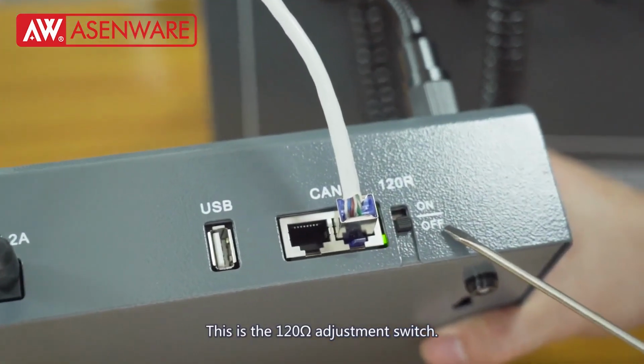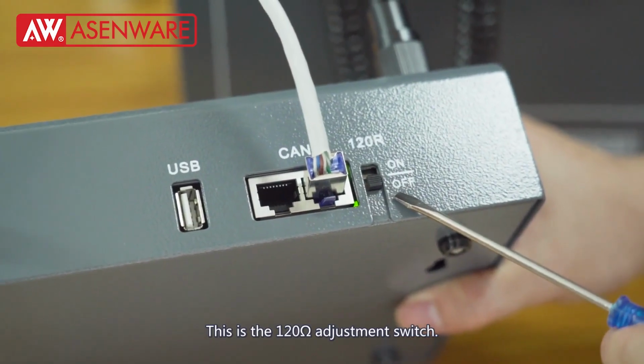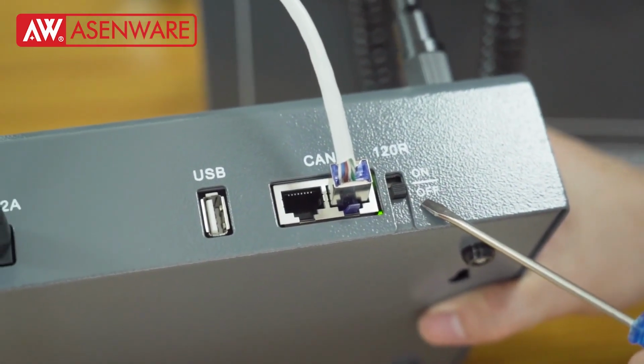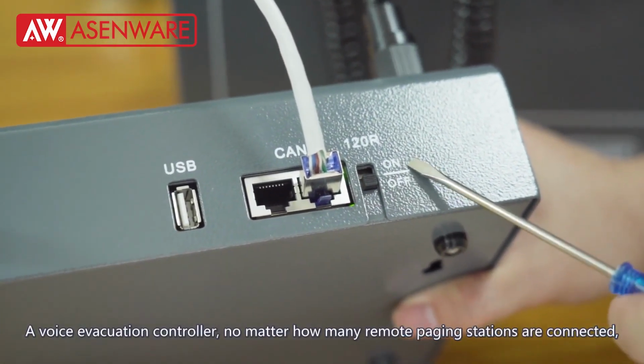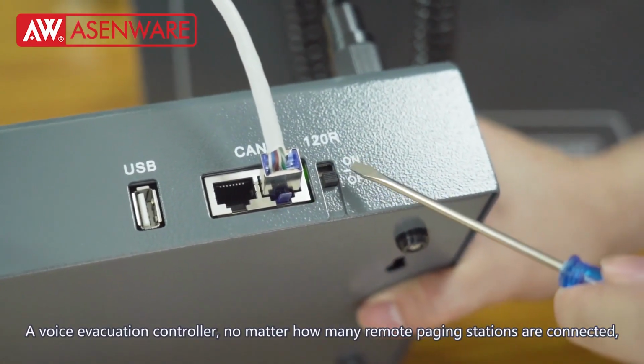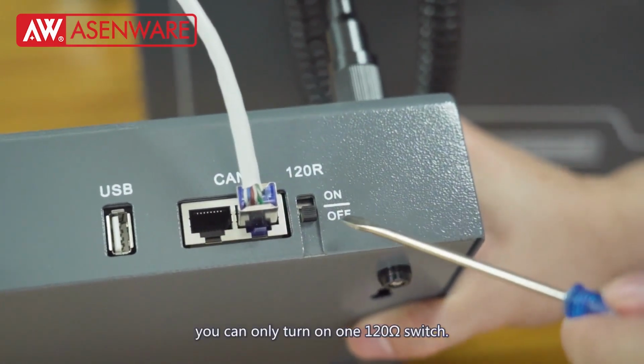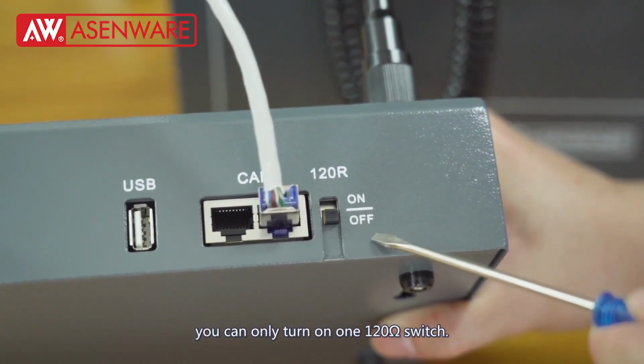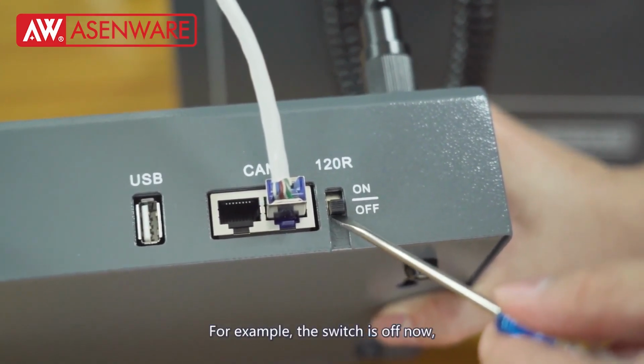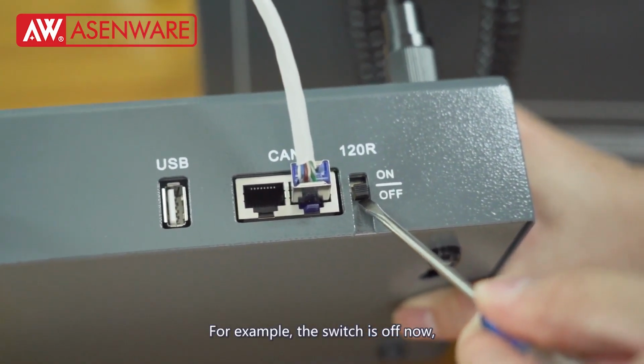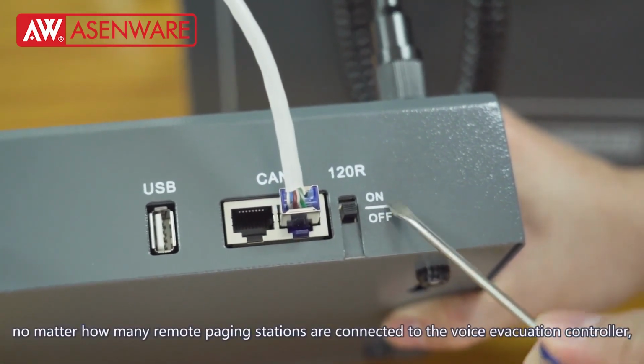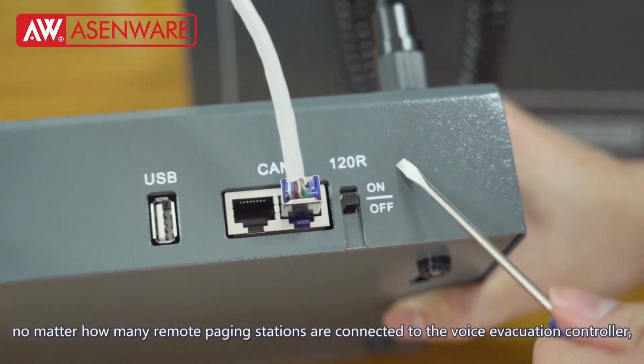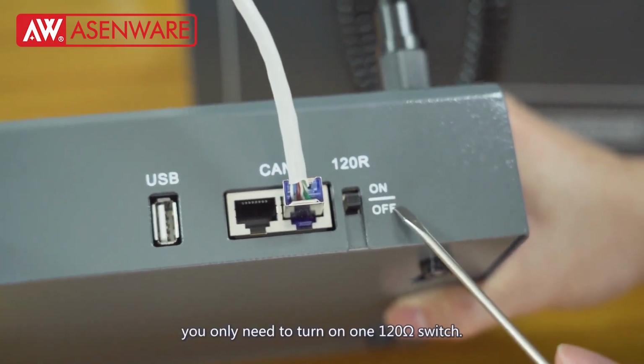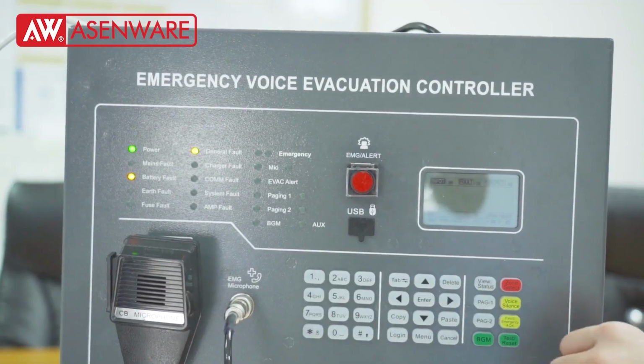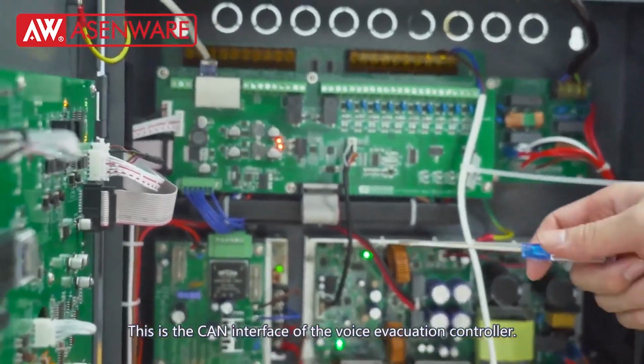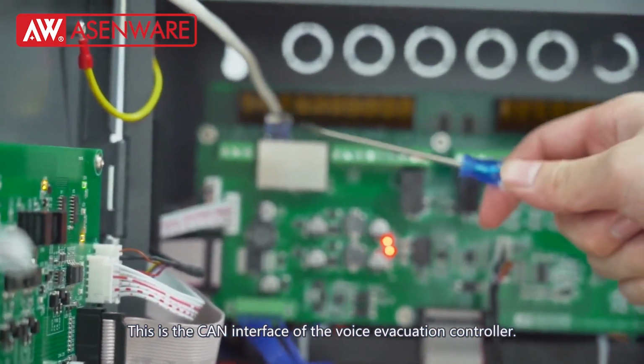This is the 120 ohm adjustment switch. A voice evacuation controller, no matter how many remote paging stations are connected, you can only turn on one 120 ohm switch. For example, the switch is off now. No matter how many remote paging stations are connected to the voice evacuation controller, you only need to turn on one 120 ohm switch. This is the CAN interface of the voice evacuation controller.